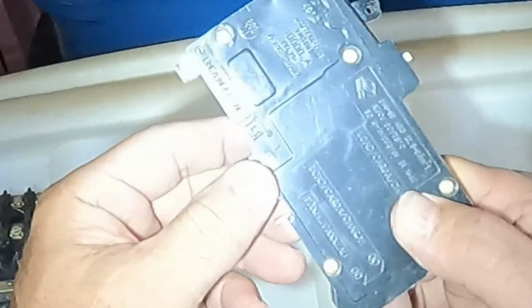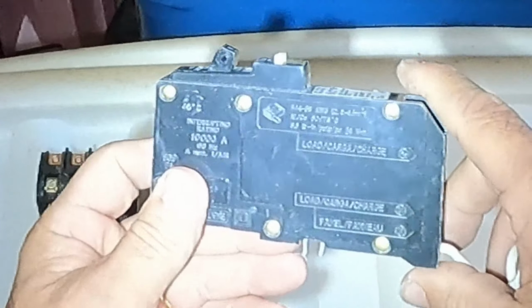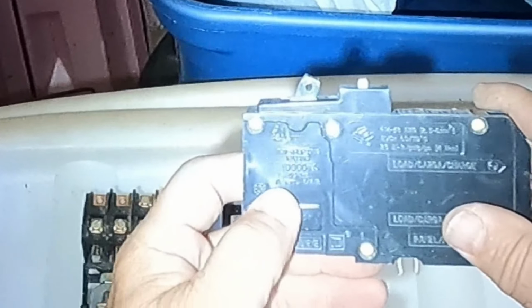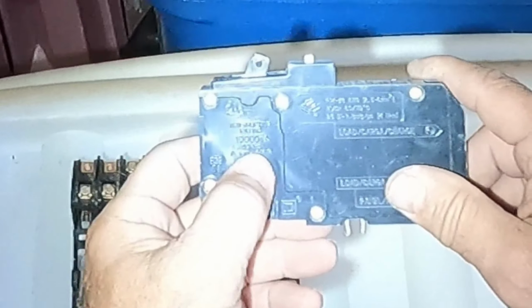Let's jump up to an arc flash breaker. And it's, again, 10,000 AIC. And it is not... It just shows 120 with the squiggly line, AC. So this is not DC.